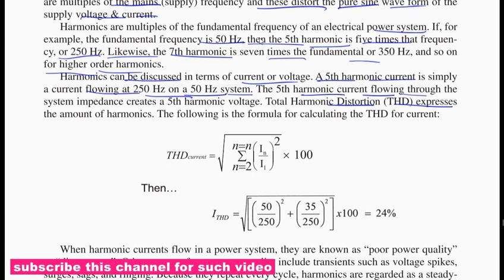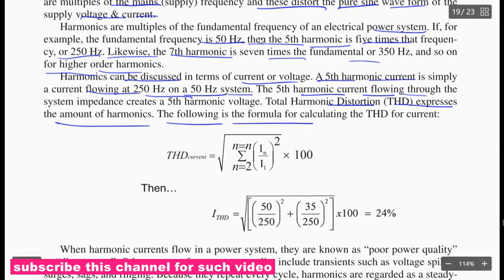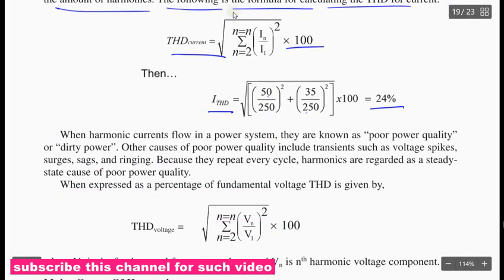Total harmonic distortion expresses the amount of harmonics, following the formula for calculating the total harmonic distortion of current. Total harmonic distortion is the square root of the sum of In squared divided by I1 squared, into 100. According to the current, that is the square root of (50 divided by 250) squared plus (35 divided by 250) squared, into 100, that is 24%. When harmonic currents flow in the power system, it is also known as poor power quality, dirty power.